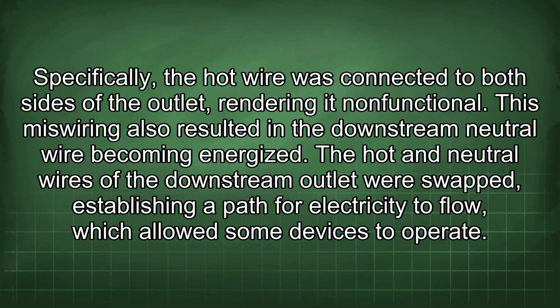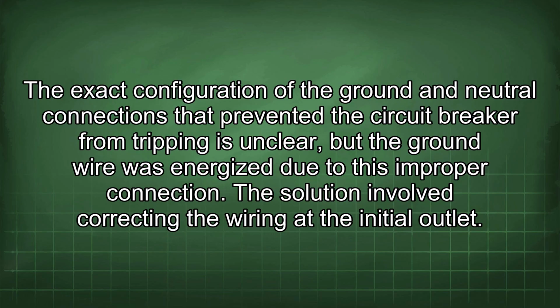The hot and neutral wires of the downstream outlet were swapped, establishing a path for electricity to flow, which allowed some devices to operate. The exact configuration of the ground and neutral connections that prevented the circuit breaker from tripping is unclear, but the ground wire was energized due to this improper connection. The solution involved correcting the wiring at the initial outlet.